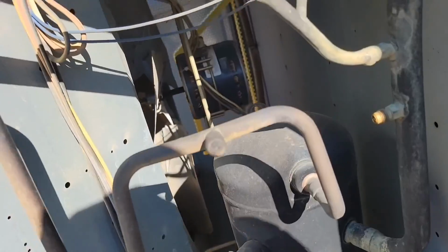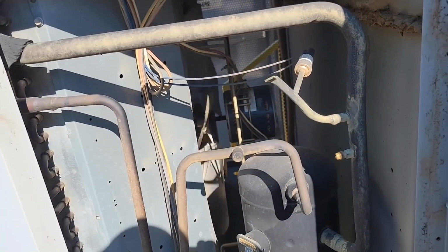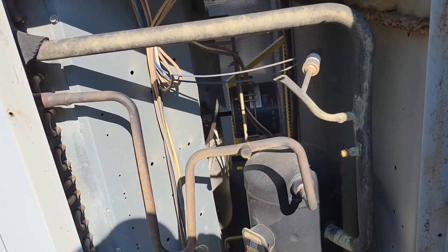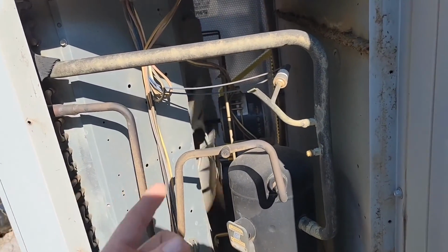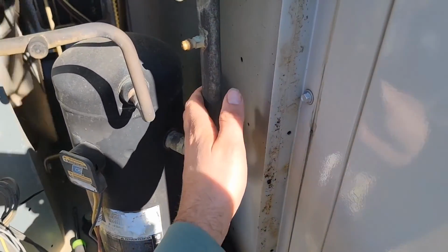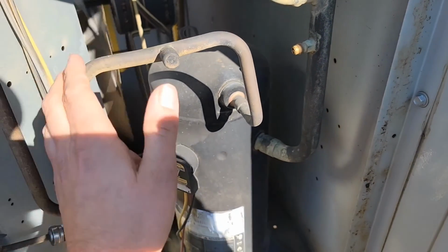So, let's go. Fan is not turning. I don't recommend what I'm about to do. Okay, so that's what's happening. It's the fan's getting locked up. Let's check the capacitor, check the bearings on the fan, and our compressor is running.